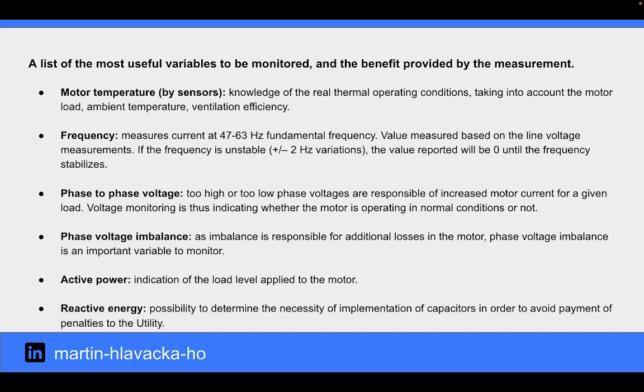Phase voltage imbalance. As imbalance is responsible for additional losses in the motor, phase voltage imbalance is an important variable to monitor. Active power. Indication of the load level applied to the motor. Reactive energy. Possibility to determine the necessity of implementation of capacitors to avoid payment of penalties to the utility.